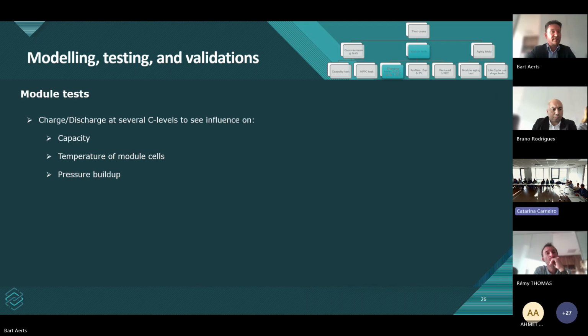Then going to the module tests. What we're going to do here is charge and discharge at several C levels to see the influence on several parameters: the capacity, the temperature of the module cells, and the pressure buildup.